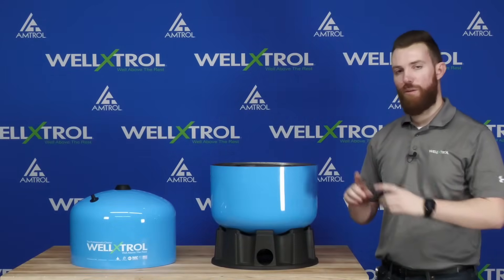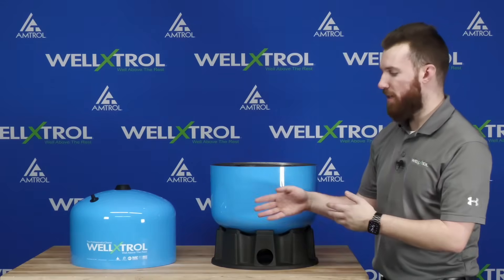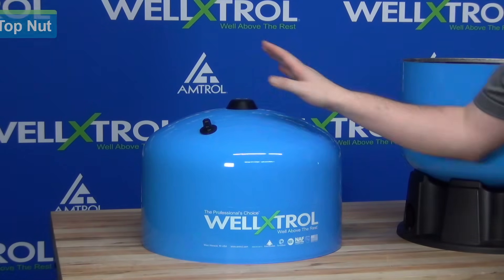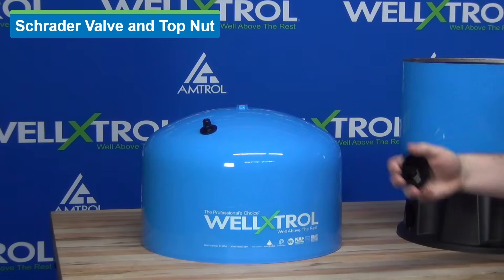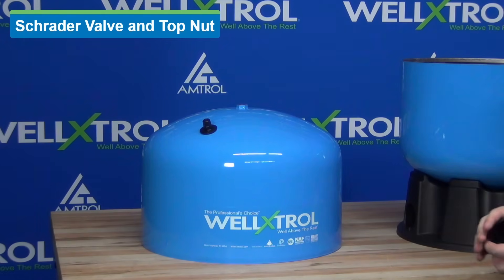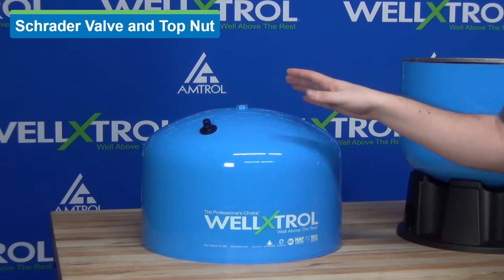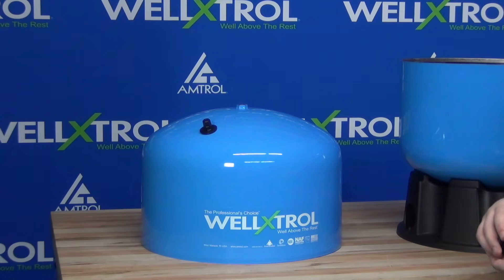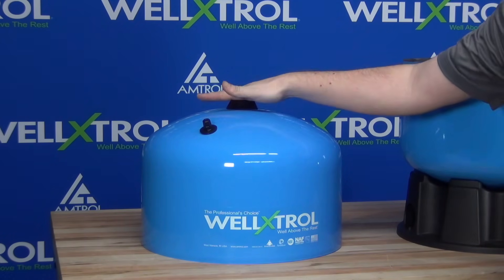Now that our water dome is complete, we're moving over to our air domes. Here I have the top of the WellXtrol tank with two pieces to talk about. The first is centered underneath this black cap, which covers a welded nut. That top nut is used for our paint hooks in the factory so we can hang the tanks for the painting process, and then it's covered in the field for corrosion resistance and aesthetics.